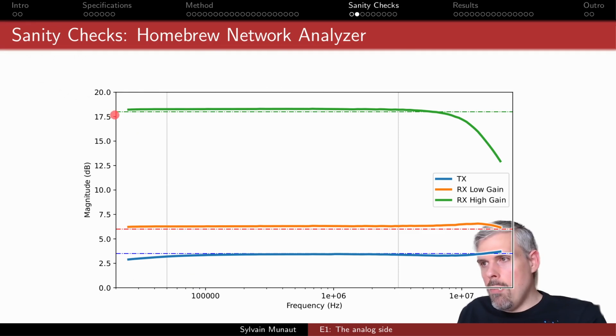If you look at the transmit, the blue line there is the transmit. The dashed line is the theoretical 3.5 dB, and we can see that we are sticking to it very well. Same thing for the receive low gain. We have slightly more gain, but it's very flat. And same thing for the receive high gain. It's also very flat and very close to the theoretical value of 18 dB. So really no problem on that side.